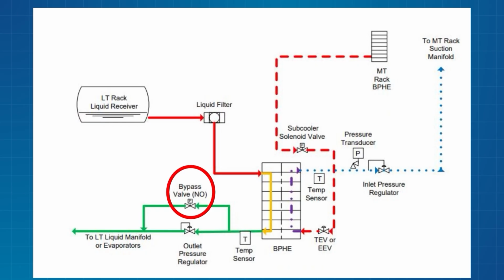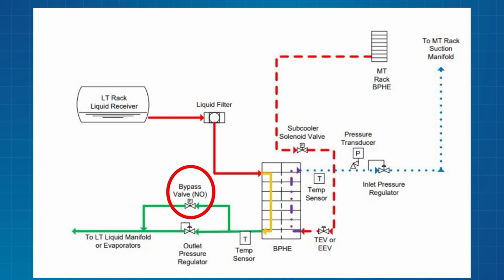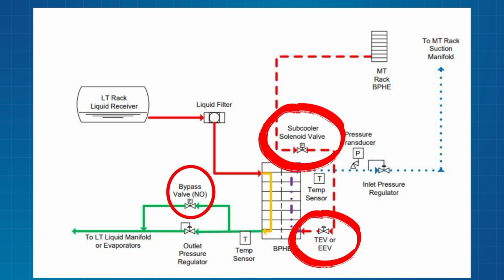Now my valve's not big enough. Right? Case is gonna run long. I'm gonna have high superheat. So if that happens, if my subcooler is not subcooling, I gotta open this bypass so I don't restrict that pressure, and I get my differential back up high so my valve acts the correct size. Does that make sense? So that means I'm gonna tie this solenoid into the solenoid feeding this EEV. They're gonna be tied together.